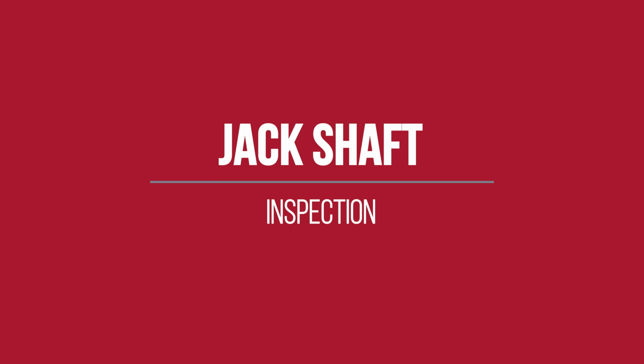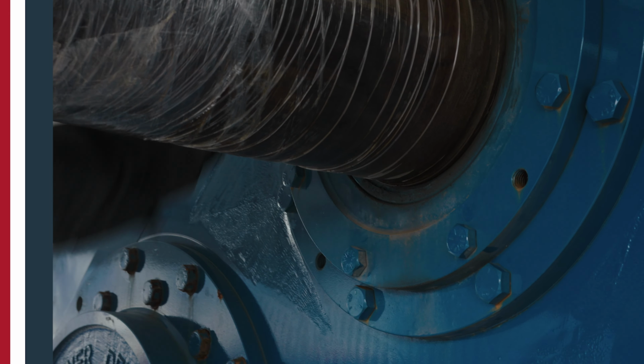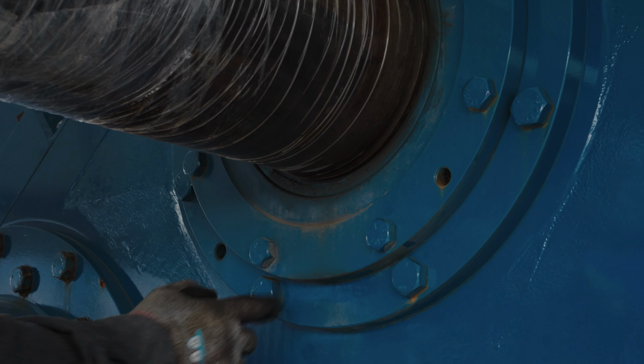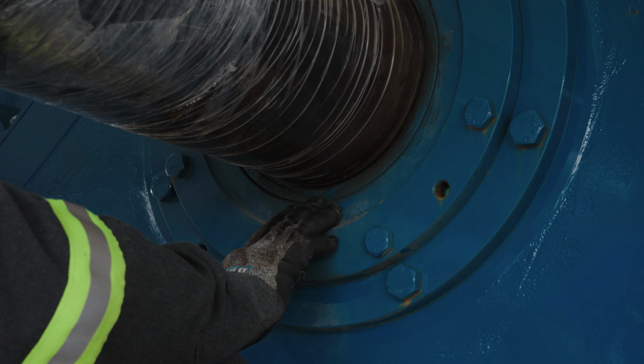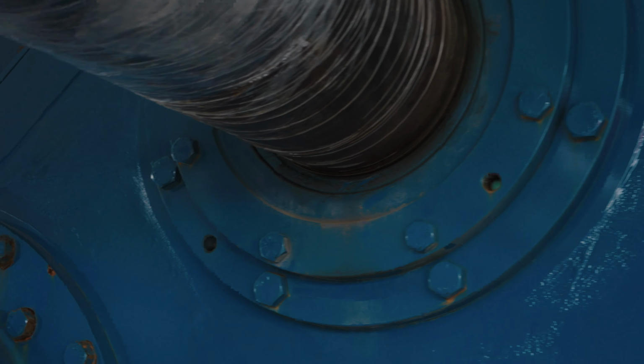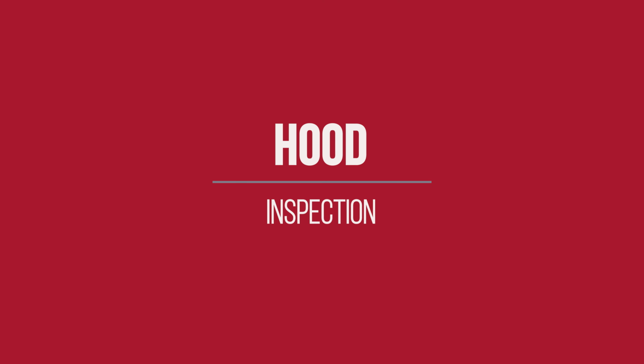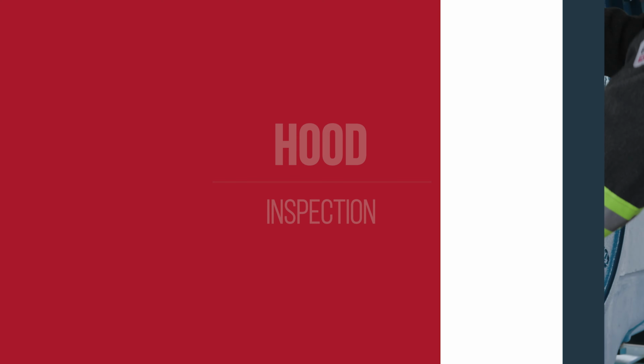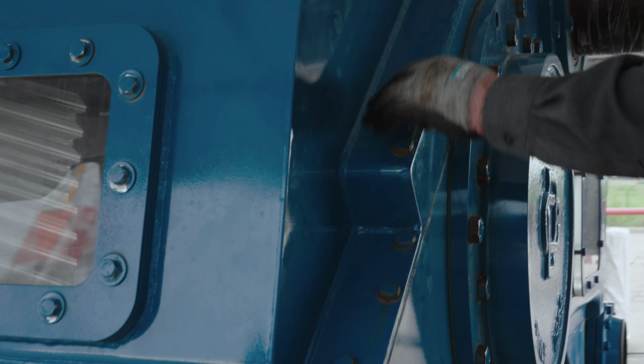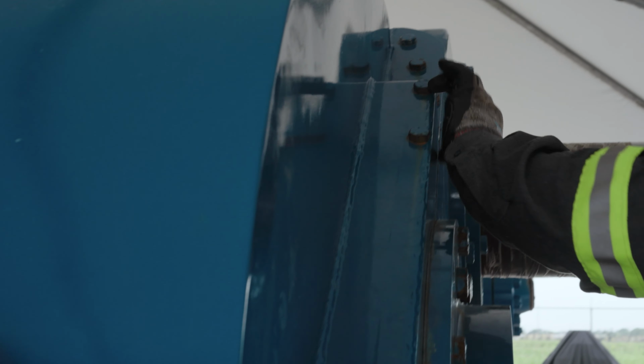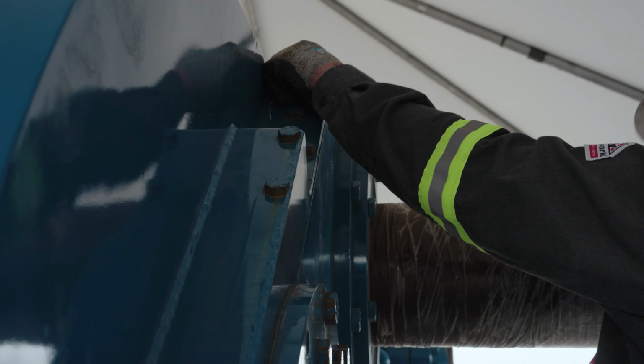On the jack shaft, you want to check for loose or broken studs or bolts and leaking gaskets. Be sure to check the jack shaft on both sides of the pump. Do not interact with the jack shaft if it is operating. Inspect the pump hood. Again, you want to check for leaky gaskets, paying close attention to the corners. Ensure all bolts are tight and not broken.